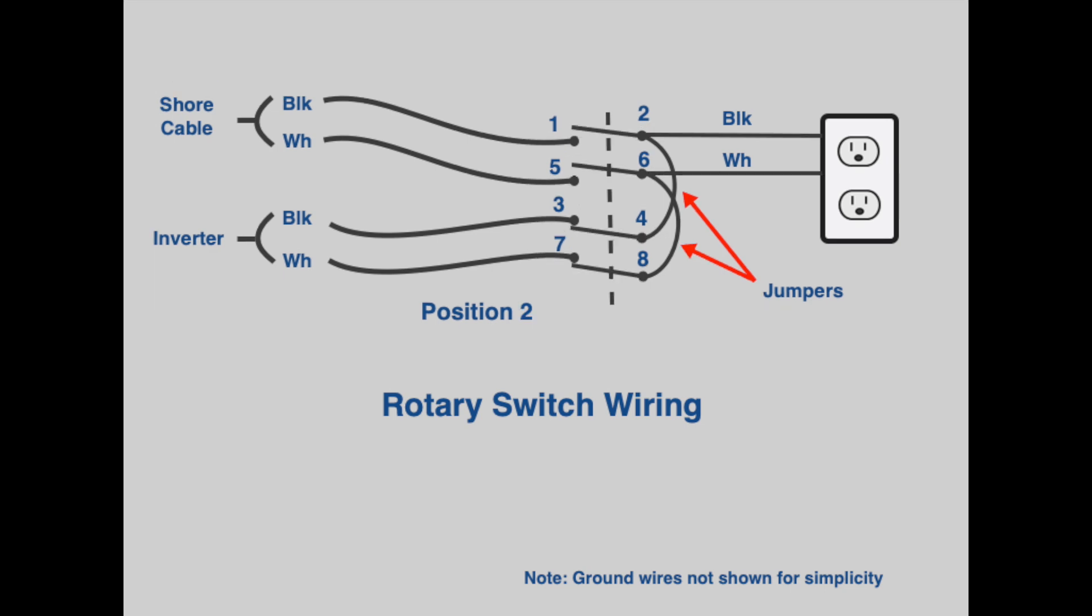When we turn the switch to position two, the shore power conductors are disconnected. The black wire from the inverter is connected to terminal three, through the switch to terminal four, then along the jumper to terminal two, and onto the house hot wire. Likewise, the inverter white conductor connects to terminal seven, through the switch to terminal eight, along the jumper to terminal six, and onto the house circuit.